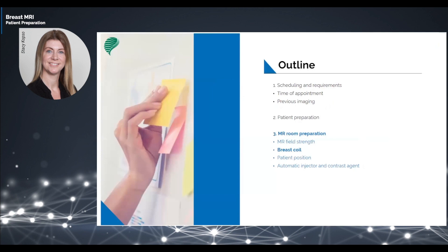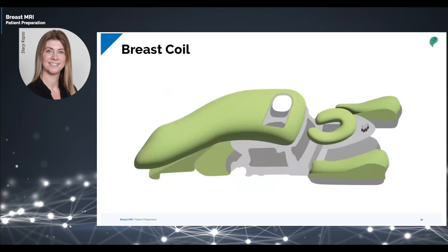Using a dedicated breast coil is mandatory in order to obtain decent diagnostic quality. A breast coil should have at least 4 channels. Modern designs have 16 channels or more, and some designs contain dedicated channels for the axillary region. In general, coils with more channels obtain a higher signal-to-noise ratio. More channels also enable the use of higher parallel imaging factors, which can increase the speed of image acquisition.